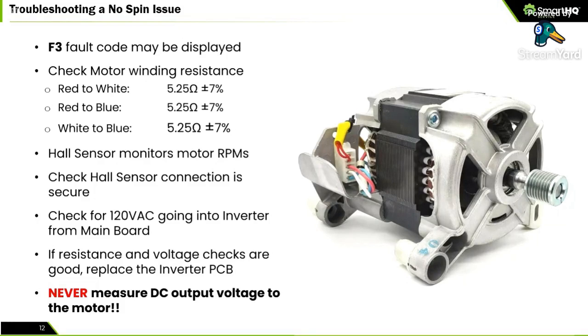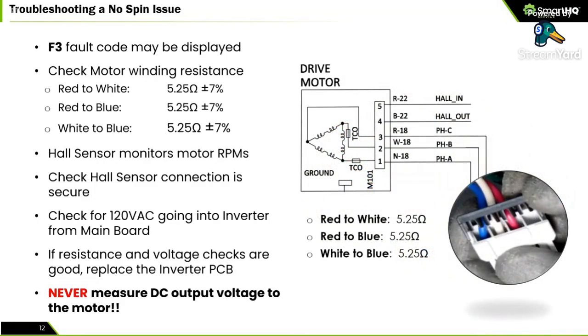So what we're going to check on the motor is the resistance on the wires. You can simply remove the wire harness and check between the red and white, or the red and blue, or the white and blue. You should be getting about 5.25 ohms of resistance, plus or minus 7%. So there's very little tolerance there, but there is a little bit of wiggle room, okay? It's just not much. So all in all, you should be getting somewhere in that neighborhood. If one reading is giving you 10 ohms and one reading is giving you 0 ohms or something crazy, that means you have a bad coil, a bad winding on the motor, and that motor would need to be replaced, okay?